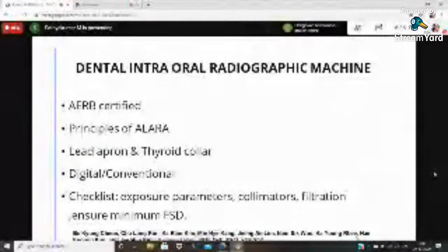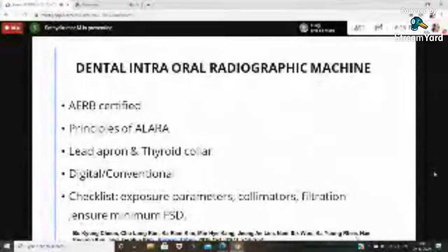Next, your X-ray machine should have an automatic timer and a cutoff control, and ensure that all the exposure parameters, your collimators, filtration, and the minimum focal spot to skin distance are followed as per AERB regulations. With the arrival of these AERB regulations, for any X-ray machine that you purchase, ensure that the machine completely follows the AERB regulation, and they issue a certificate to you that the machine is regularized by AERB.